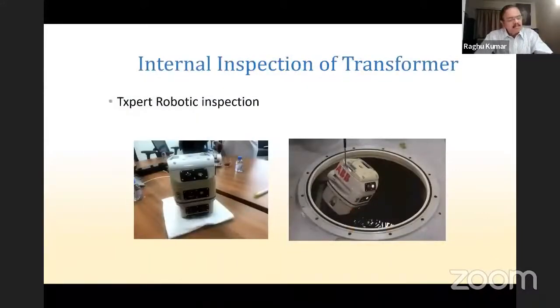This is an interesting part. The internal inspection. Suppose you have identified a fault in the condition monitoring, and you know it is inside the transformer. How do you solve the problem? Normally the OEM has to solve the issue, but the problem is we don't know exactly what the problem is internally. One way of solving the problem is giving a contract directly without knowing what the issue is, where the contract value will be very high because the tenderer doesn't know what exactly the problem is. He is expecting the worst and will charge you heavily.